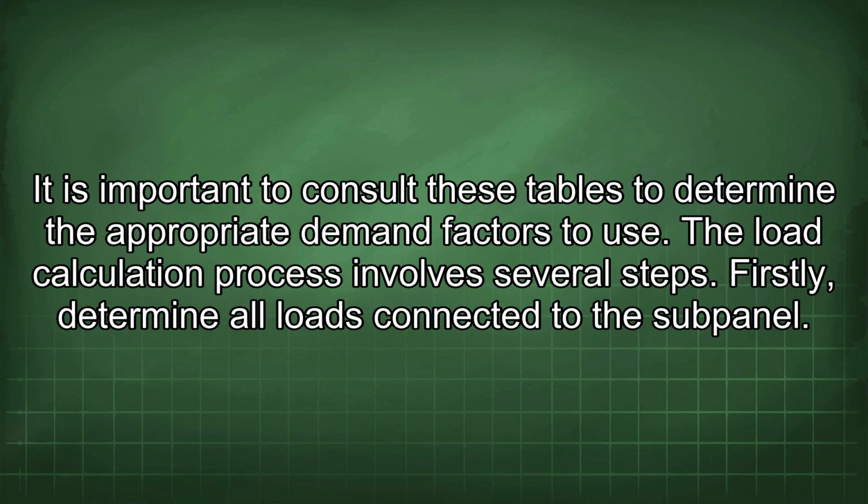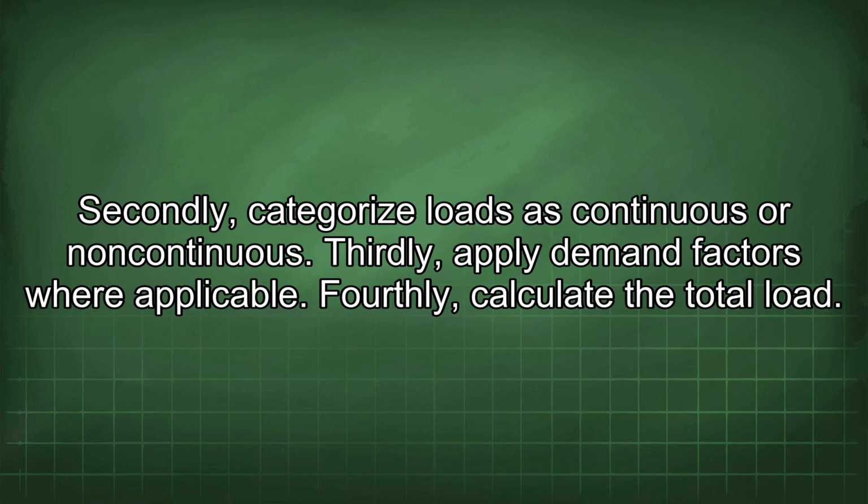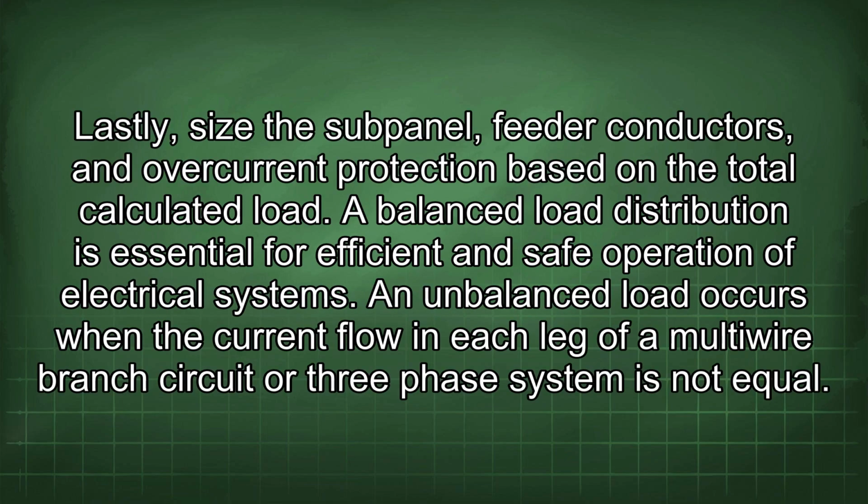The load calculation process involves several steps. Firstly, determine all loads connected to the subpanel. Secondly, categorize loads as continuous or non-continuous. Thirdly, apply demand factors where applicable. Fourthly, calculate the total load. Lastly, size the subpanel, feeder conductors, and overcurrent protection based on the total calculated load.